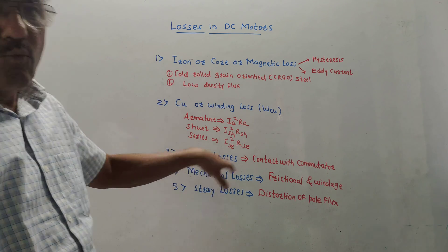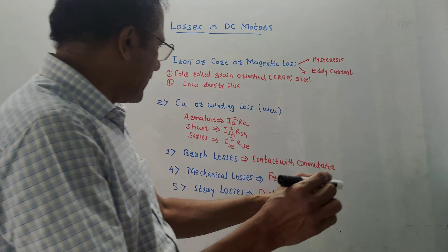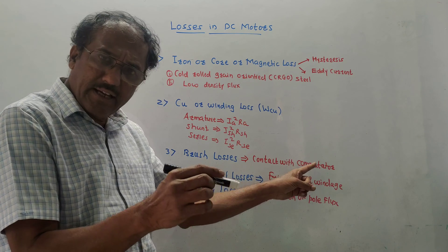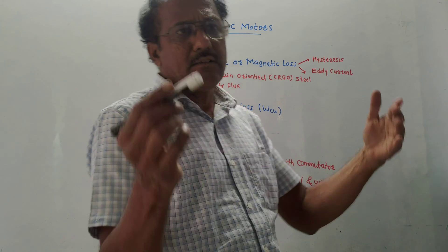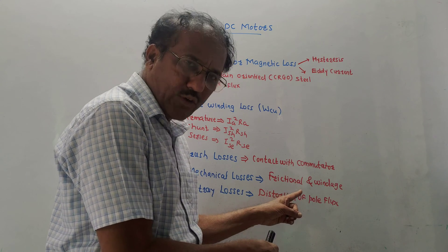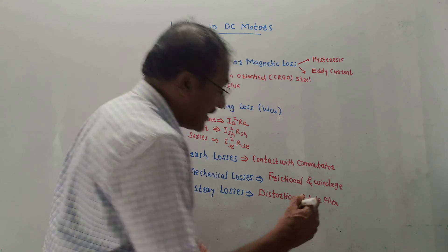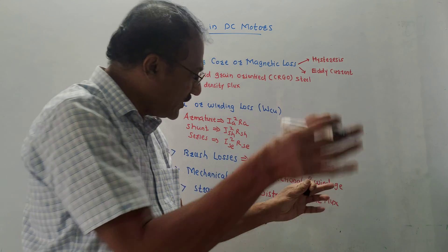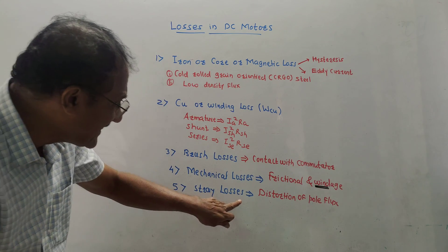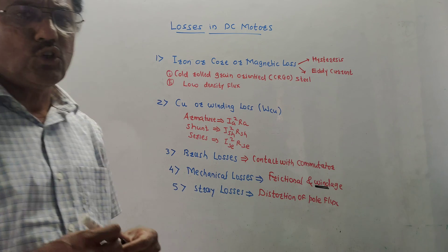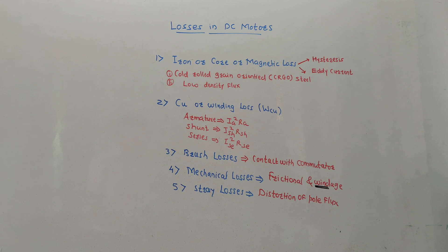Third type is brush loss — the brushes are in contact with the commutator, so due to this contact there can be losses. Fourth type is mechanical losses — due to rotating parts causing friction, also known as frictional loss — and windage loss, which occurs due to air gap between the rotating part and machine enclosure. Last type is stray loss, due to distortion of the pole flux.